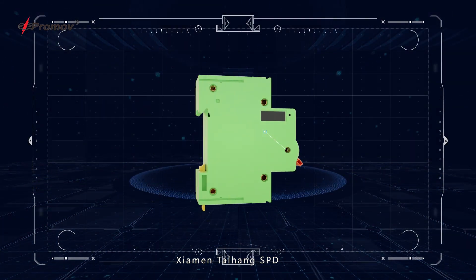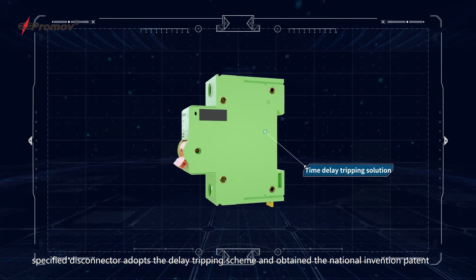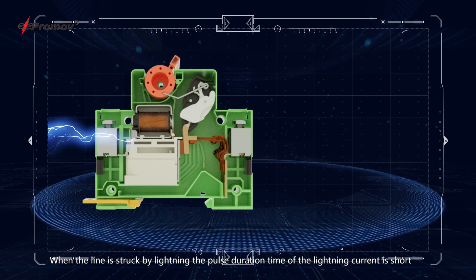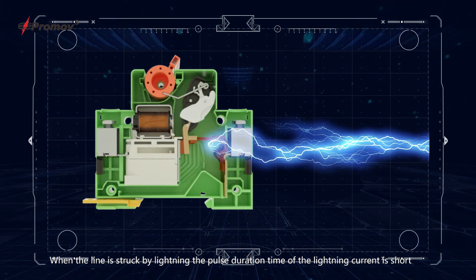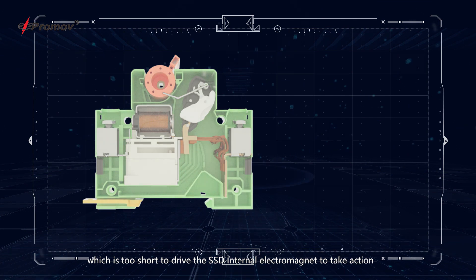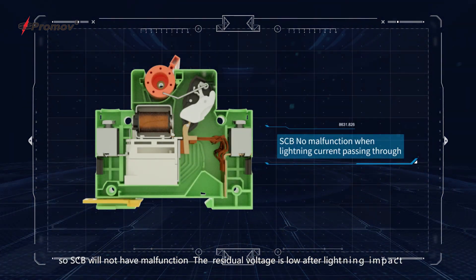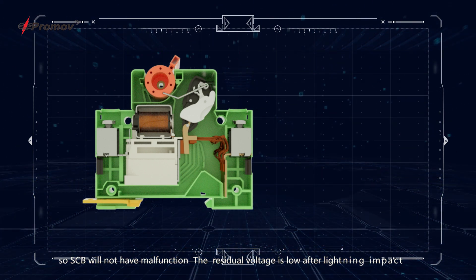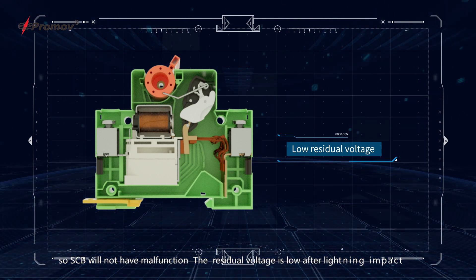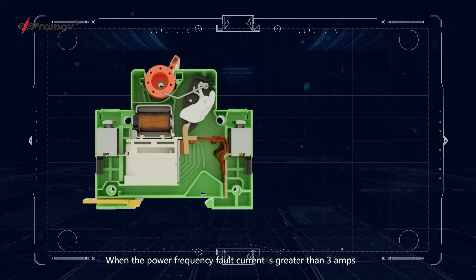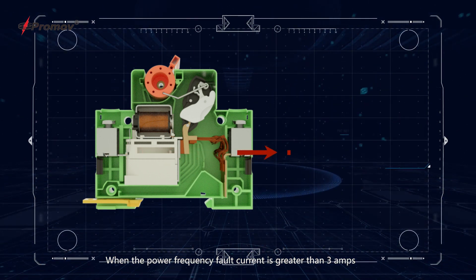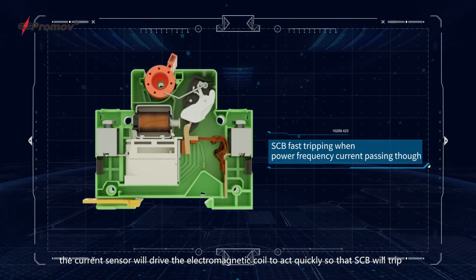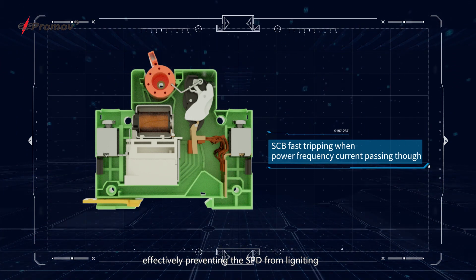Xiamen Taihang's SPD-specific disconnector adopts a delayed tripping scheme and has obtained a national invention patent. When a line is struck by lightning, the pulse duration of the lightning is very short — too short to drive the SCB's internal electromagnet to take action — so the SCB will not malfunction. The residual voltage is low after lightning impact. When the power frequency fault current is greater than 3 amperes, the current sensor drives the electromagnetic coil to act quickly, causing the SCB to trip and effectively preventing the SPD from igniting.